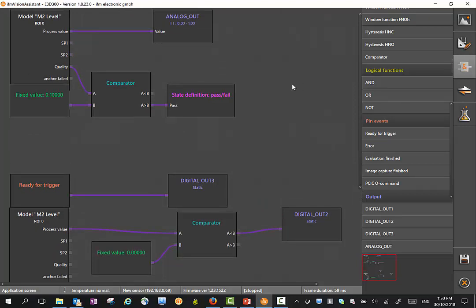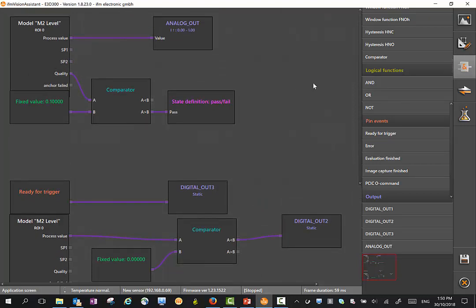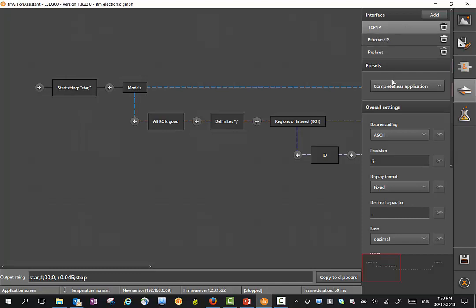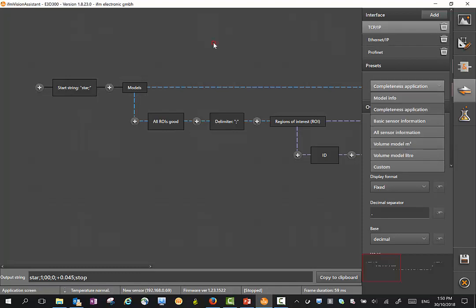Once you're happy with your outputs here, we can actually set our process interface, our Ethernet string. You'll see there's a number of variants we have here: TCP IP, Ethernet IP, PROFINET. We can define some different string depending on the information that you want to see. For instance, completeness, basic sensor information, all sensor information, volume in liters or cubic meters, or we can do a custom string.